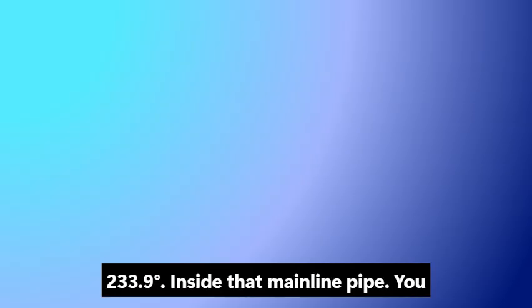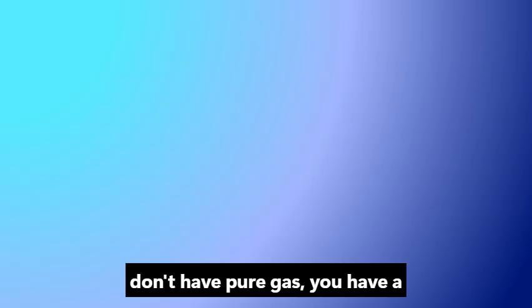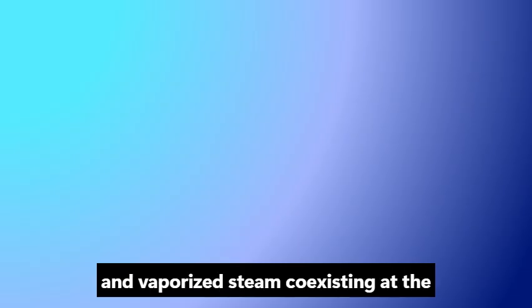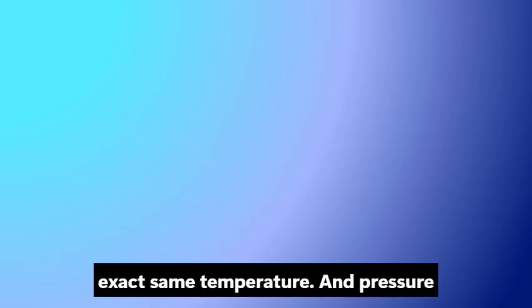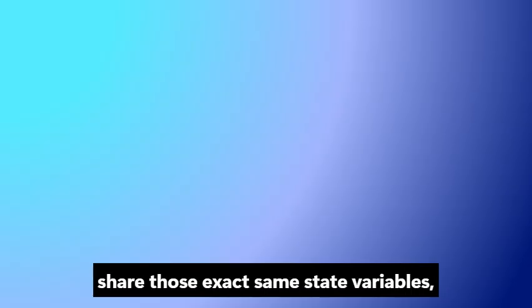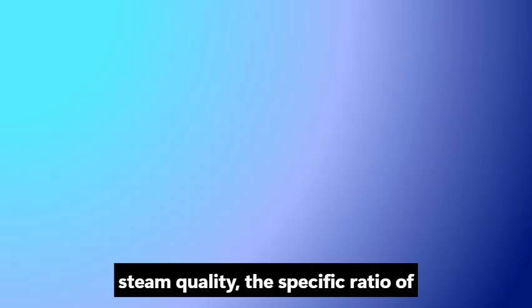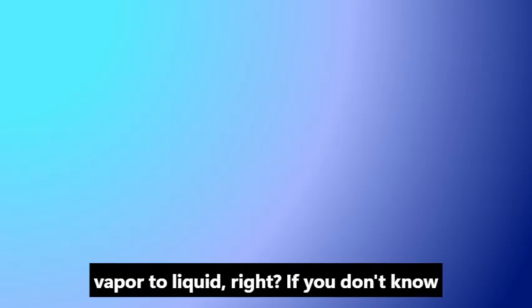At 30 bar, water boils at 233.9 degrees. Inside that mainline pipe, you don't have pure gas. You have a chaotic boiling mixture of liquid water and vaporized steam coexisting at the exact same temperature and pressure. Saturated steam. Yes, and because they share those exact same state variables, your pressure gauge and your thermometer are entirely useless for telling you the steam quality. The specific ratio of vapor to liquid?